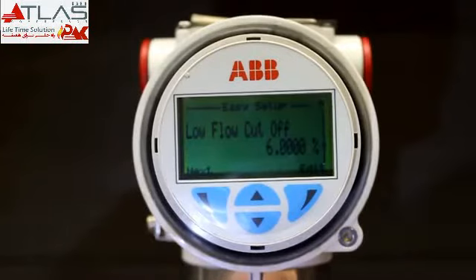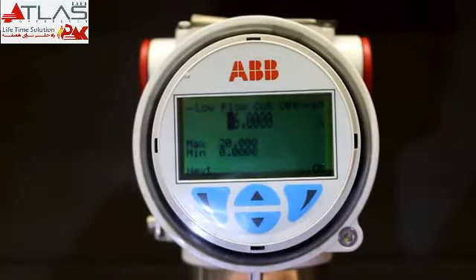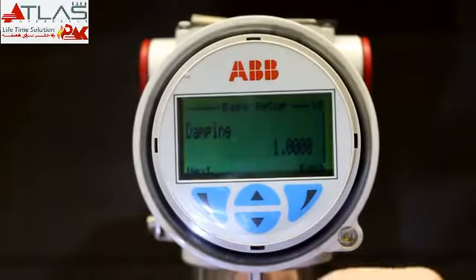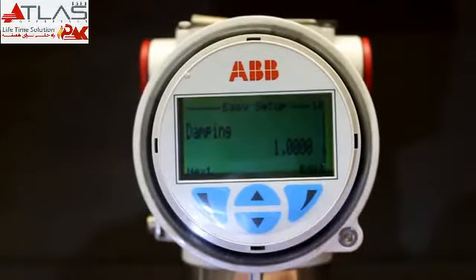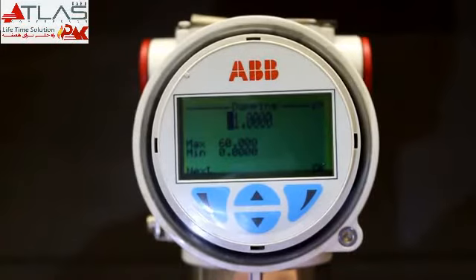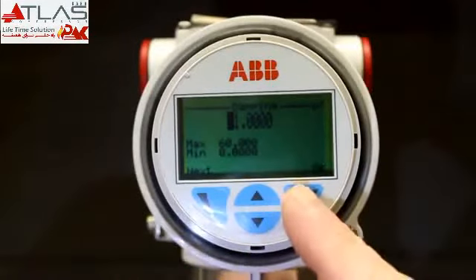Low flow cutoff is at 6%. You can change that from 0 to 20% as well. We'll leave that at 6%. Damping is at 1 second. You can edit that as well, from 0 to 60 seconds for the maximum damping.